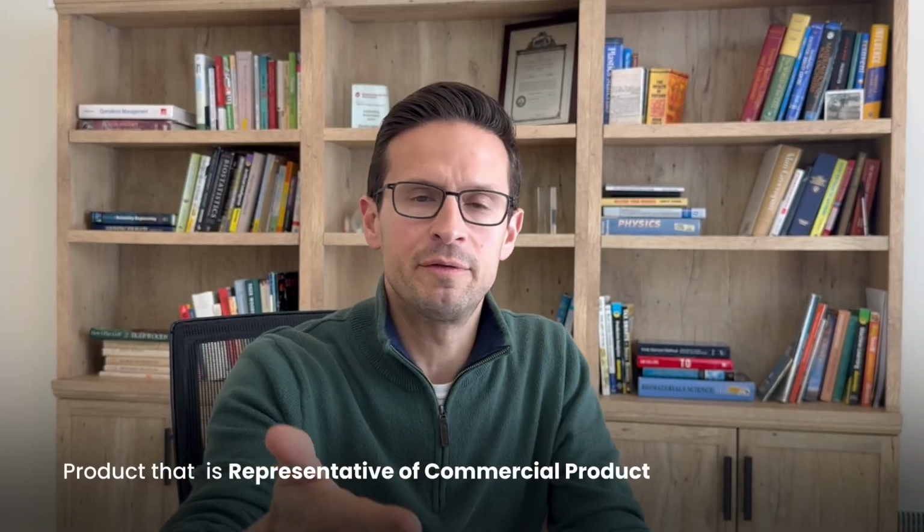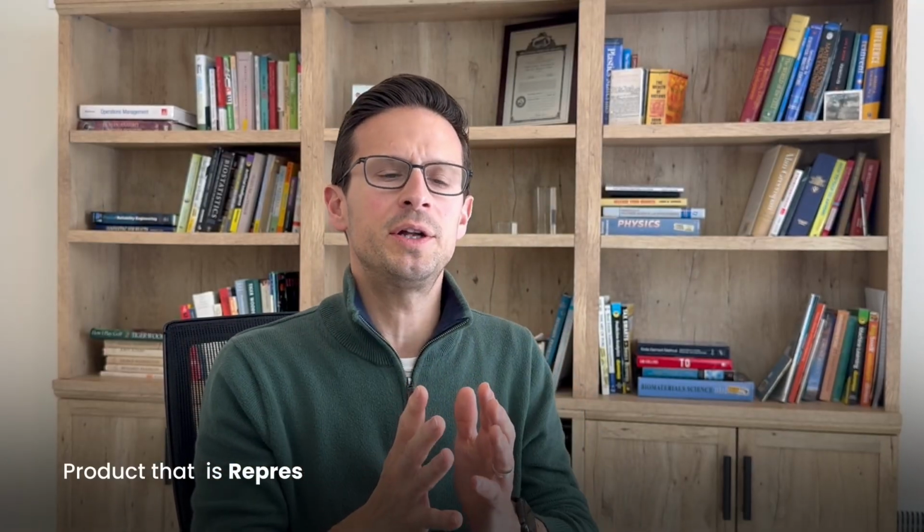The other tip I will give is there's a requirement that V&V should be done on product that is representative of commercial product. Now, this is always a big challenge because you may have not scaled up your manufacturing process. That's normally the case. So just be aware that however the products were manufactured, including the materials, including the manufacturing process, however they were manufactured for design verification, any changes you make when you scale up, you're going to have to do an impact assessment, and anything that could impact the V&V, you may have to redo.